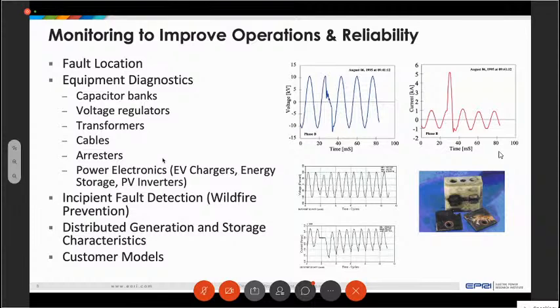The picture on the right is part of a voltage regulator that failed. That was an example of an event in Texas, and the waveforms next to it are from the power quality monitoring at one of the customers served from that substation. And they noticed this very momentary voltage sag, and if you look at the monitoring of the substation current, you see that there was actually a short period where the current was interrupted. That straight line on that waveform.